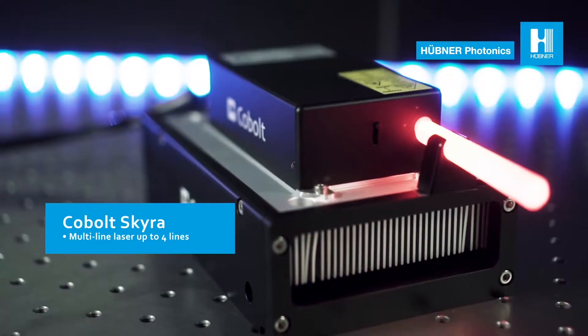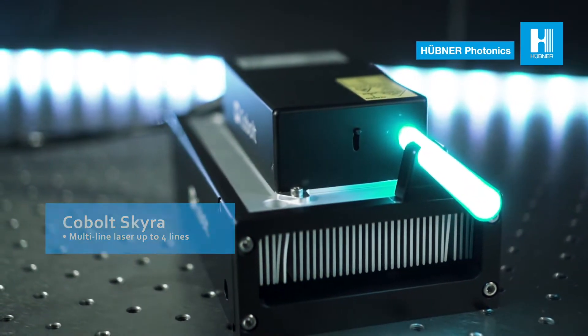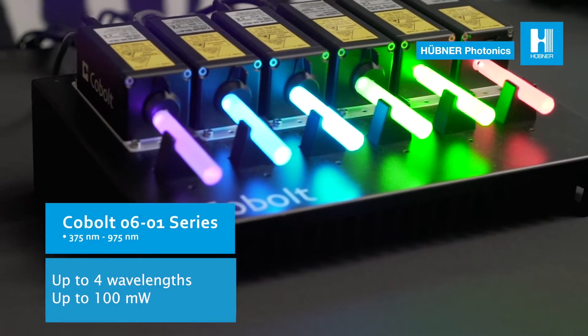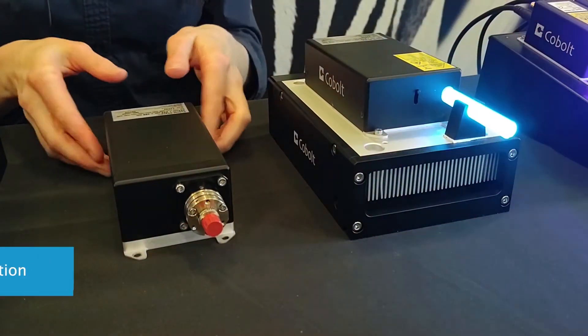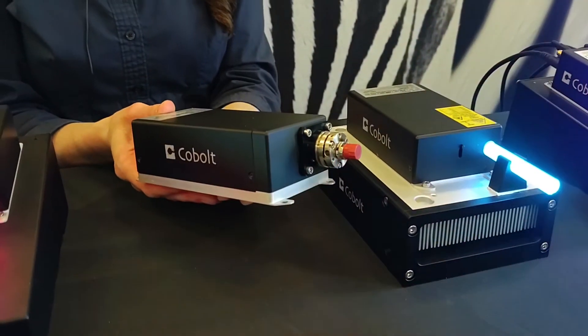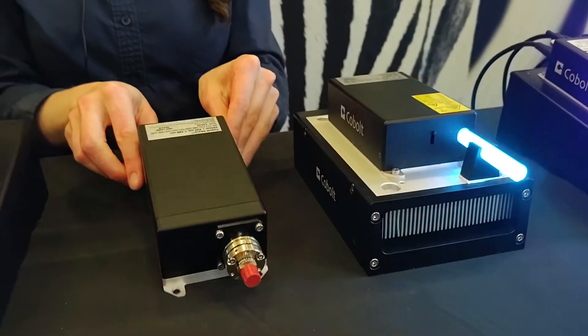The Cobolt Skyra is a permanently aligned, compact, multi-line laser which is ideally suited for light sheet microscopy. It can include up to four wavelengths with up to 100 milliwatts of output power per line and fully integrated control electronics. It is also available fiber coupled with single mode polarization maintaining fiber coupling directly on the laser head to deliver reliable and stable laser performance precisely into the optical design of the microscope.